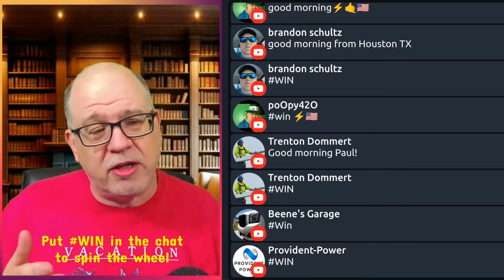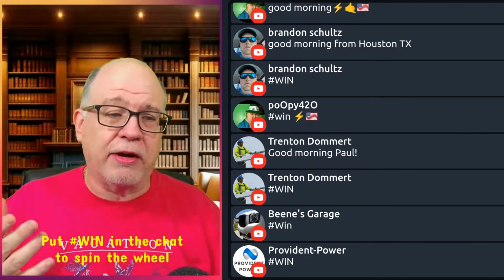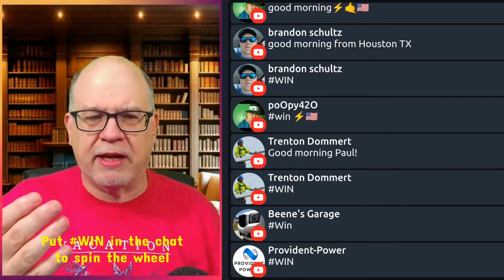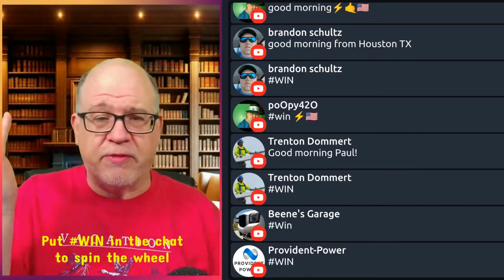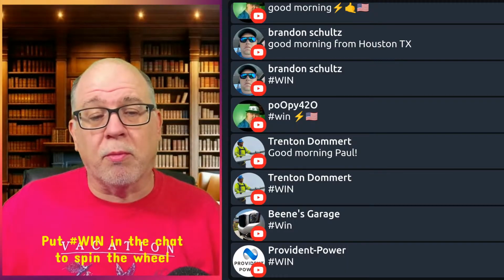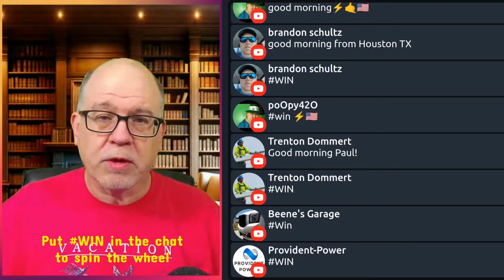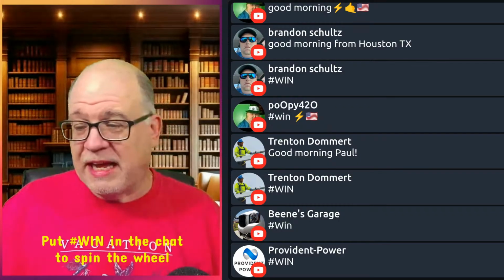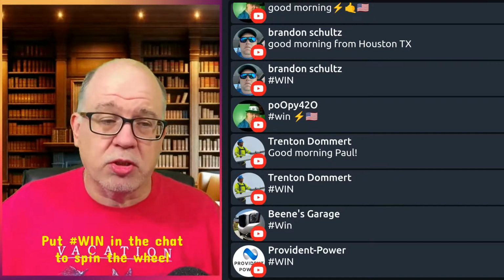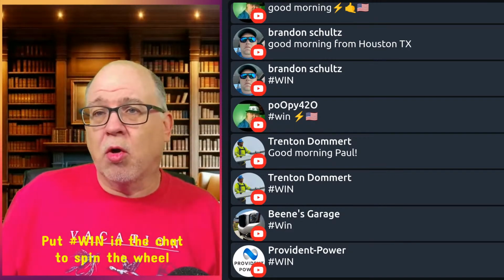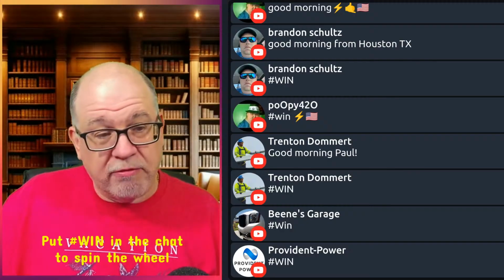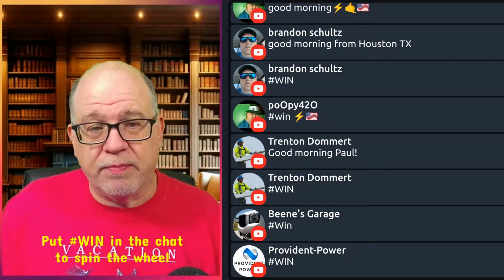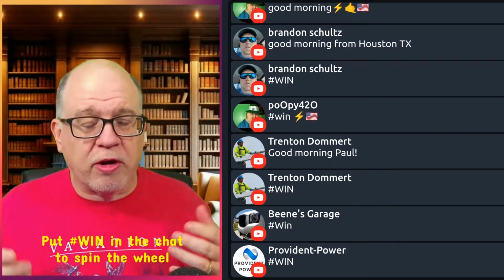Now, there are some people that say, I'm not going to do that. At Encore Wire, by the way, we make MC cable, and since the conductor's already in there, we make products called, and we're not the only ones, other manufacturers do as well, multi-neutral or multi-circuit. What's the difference? Multi-circuit means you have multiple circuits sharing the neutral. So you might have a cable that has a black, red, blue, and it might only have one white in there. Or it might have black, red, blue, and a white, and another white in there with a colored stripe on it. So it's multiple circuits sharing a neutral.